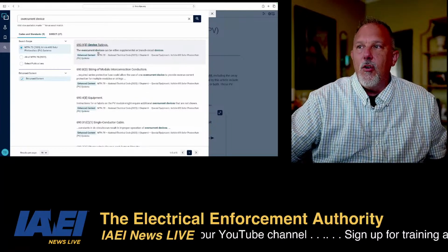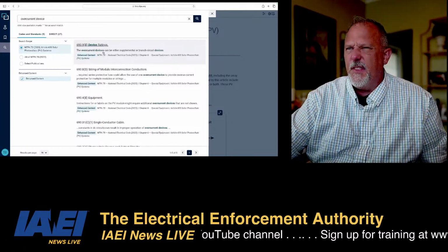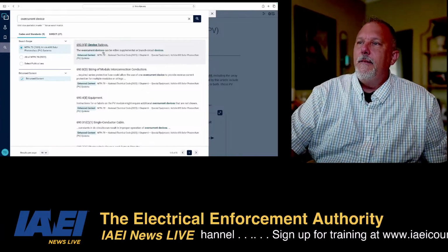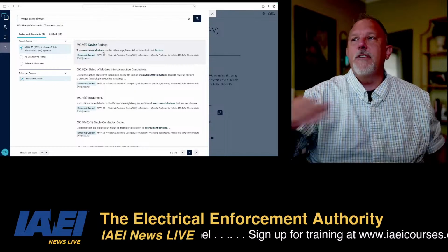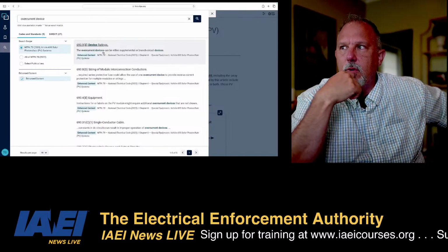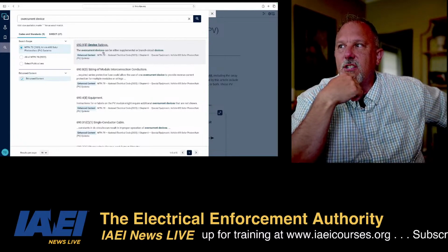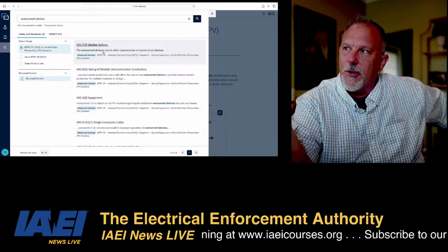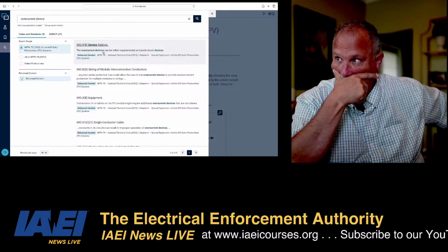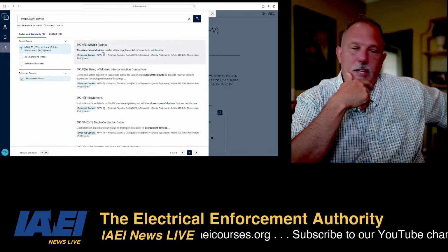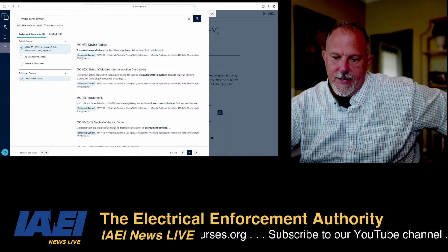690.9(B). The overcurrent devices? That's bad English. Overcurrent devices can be either supplemental or branch circuit devices. They didn't even use the proper term. They should have said branch circuit overcurrent protective devices. So they use it in 690.9.